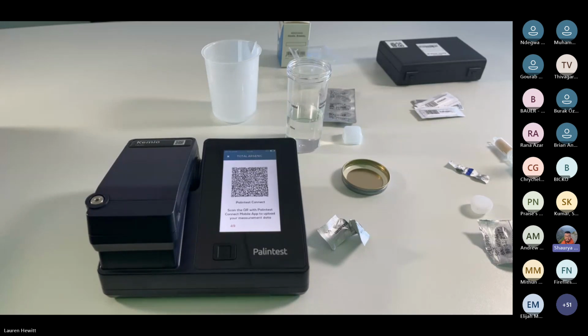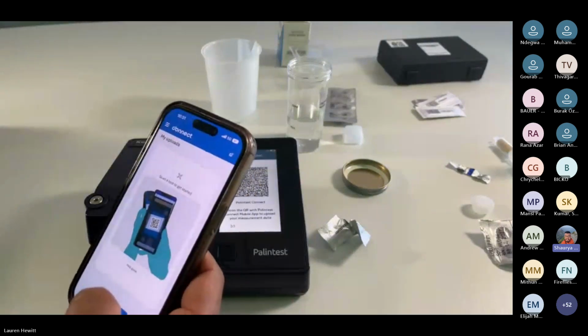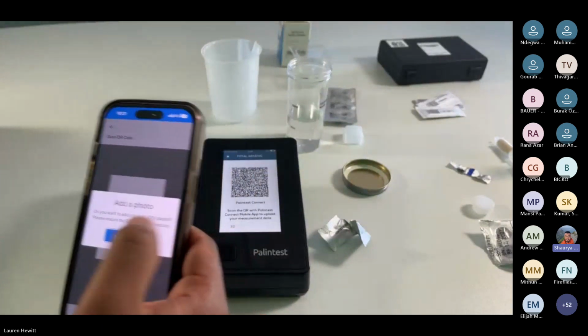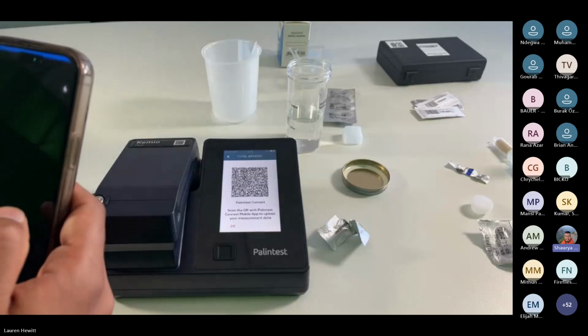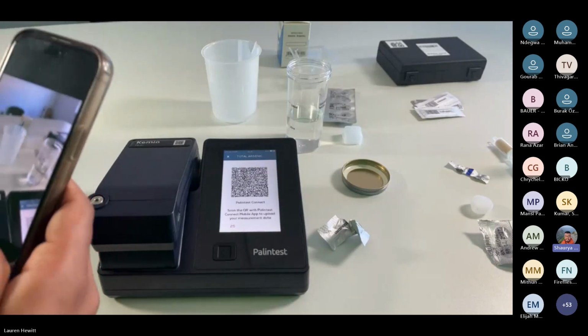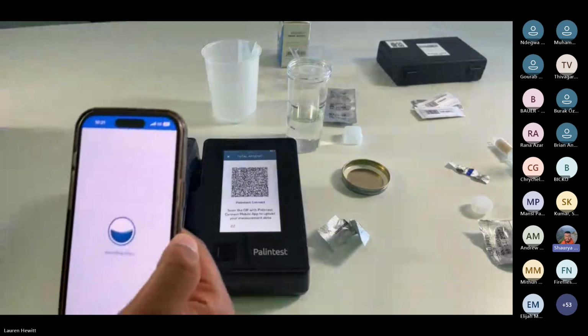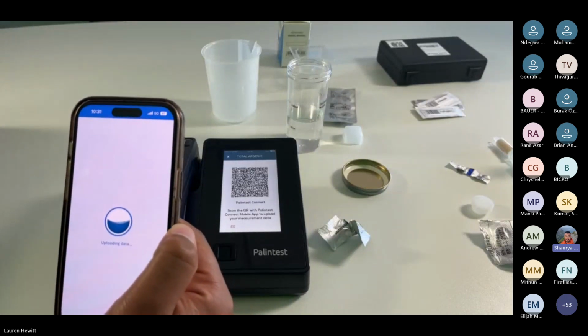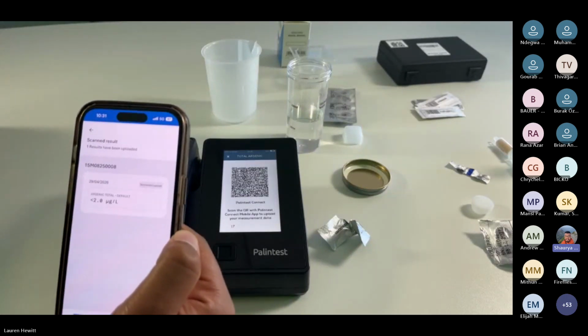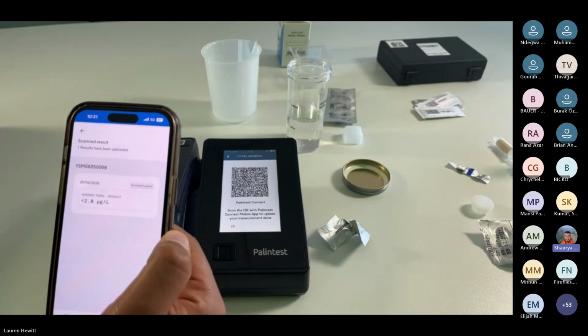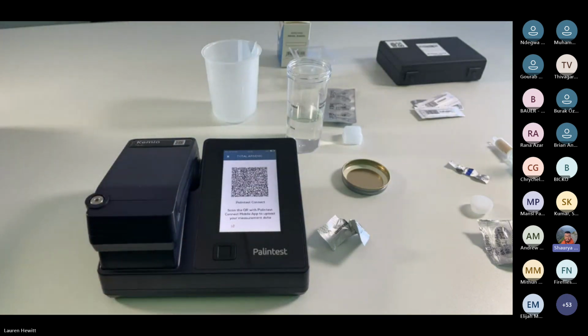Lauren, there was a question in the chat. Please tell us about the effect on the arsenic result if there is interference from iron, pH, turbidity. So this can be different across all of those. If you do have highly turbid samples, it is recommended to filter those out. It's not affected by anything below 1 NTU, but turbidity can affect it. The sensor is unaffected by any sort of floating particles in there. If it is a metal interferent, most metal interferents are removed by the ion exchange cartridge, and we do have studies on this that we're happy to share with all known interferences with this testing after this call.